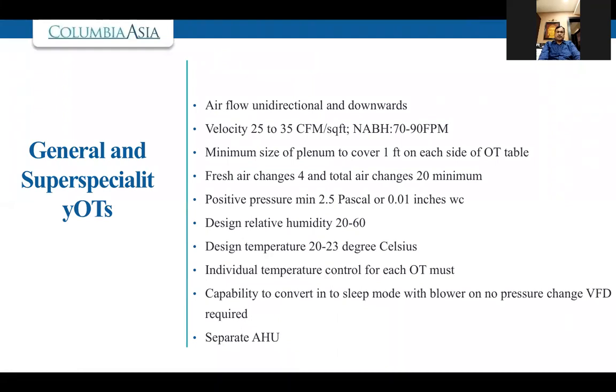So airflow should be unidirectional and downwards. It does not mention specifically laminar flow. Please do not misunderstand this particular wording. This has been designed specifically. Everywhere you need not insist on laminar flow. But generally, if it is coming onto the operation table, that is acceptable.